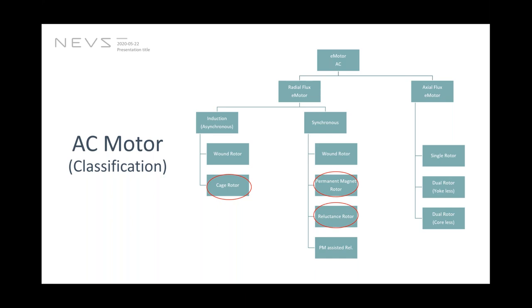But with regard to other industrial applications and HVAC, compactness and torque density might not be the selecting criteria or even a point of interest, because you do not have a space confinement or those specific requirements as we have in the automotive market. So although axial flux machine is not at the current stage so attractive to the HVAC application or other industrial application, we have on the other hand radial flux motors, which can be divided into asynchronous and synchronous. Basically, asynchronous means that the rotor of the motor will always be out of synchronization with respect to the stator magnetic field, which I will explain in the next slide.